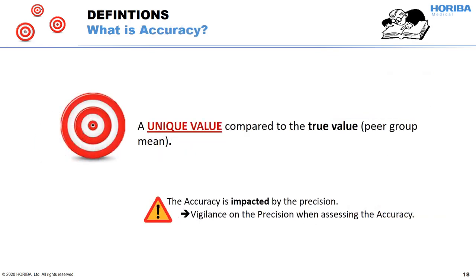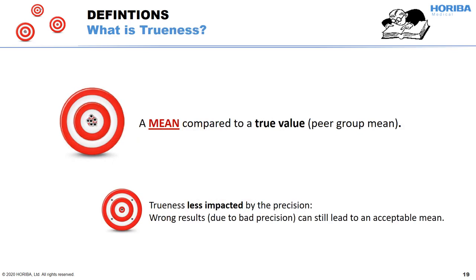Accuracy is the comparison between one unique value and the true value. But as you have only one unique value, a lack of precision could directly impact the results. It is then highly recommended to check the precision before assessing the accuracy. Trueness is the comparison between a mean of results and the true value. But if we have several imprecise results, the mean could still be acceptable — so the mean is not really impacted by the precision of the results.